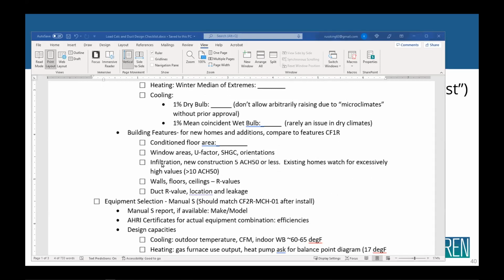That's how leaky a house is. In an existing home, the leakage of a house could be 30% of your total load if the house is really leaky. One of the things we always recommend for an existing home is to tighten up the house as part of changing out the equipment.